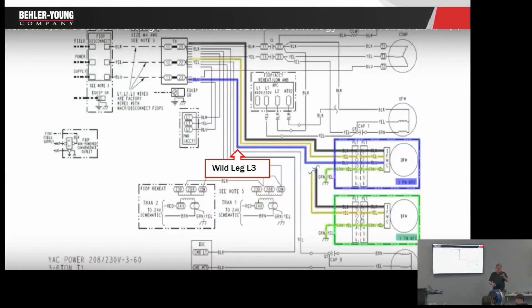Okay, wild leg. Does everybody know what a wild leg is? If you don't, a lot of older areas, especially industrial, had what was called a wild leg. So L1 to ground, 110, L2 to ground, 110, L3 to ground, 208, 210, called a wild leg, or stinger leg. If you have a wild leg, it has to go on blue L3. Why? Well, I asked that question too, and they gave me what sounds like a legit answer. I'll take their word for it.